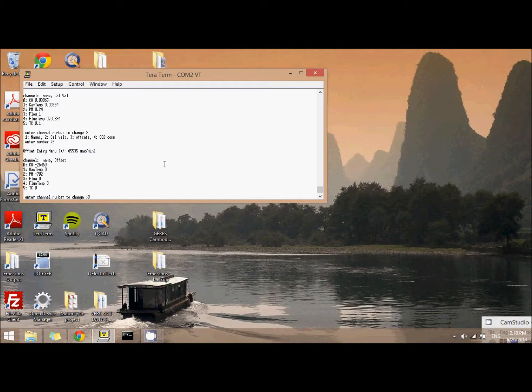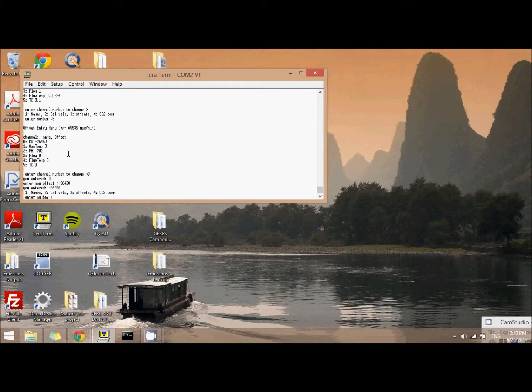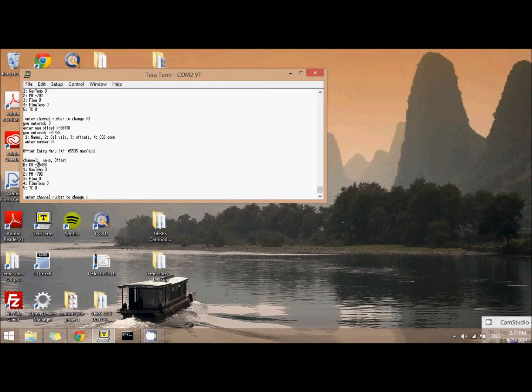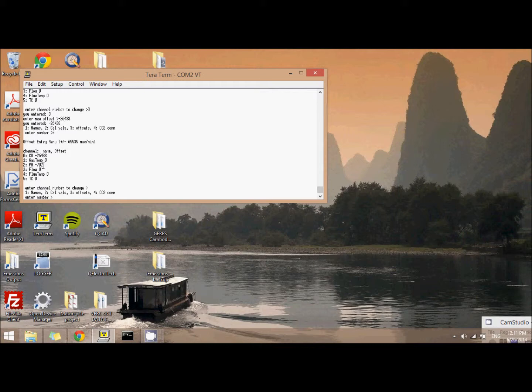So I'm going to go to channel 0, which is the channel for the CO, and now I get to enter my new offset. So I'm just going to subtract -31 from this current number to get, let's see here, it'll be -26438 as my new offset, because remember I'm subtracting a negative number, so it's going to be a little closer to 0. I press enter, and now again, just like the calibration value, I can check my offset. So I enter menu value 3, and there I see my new CO offset is entered and ready to go. And that's it. I press enter to get back to the main menu, and that's all I have to do. I can turn off my sensor box, and I've just completed my calibration procedure.